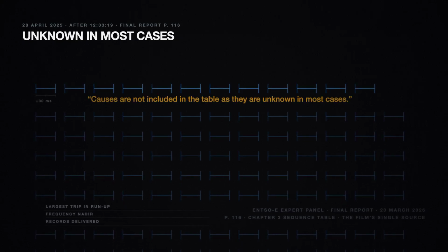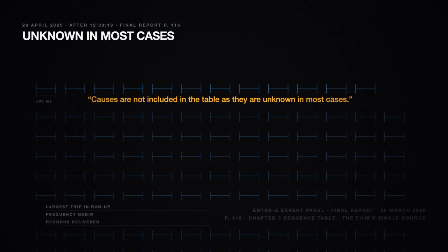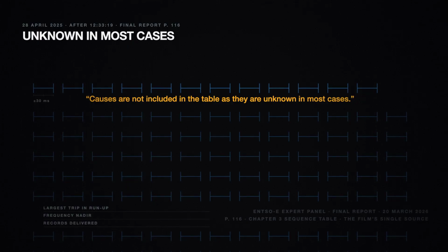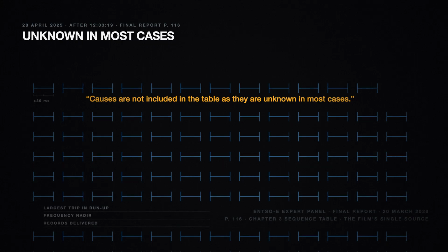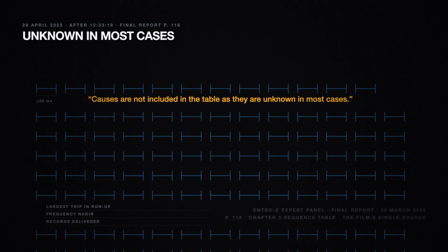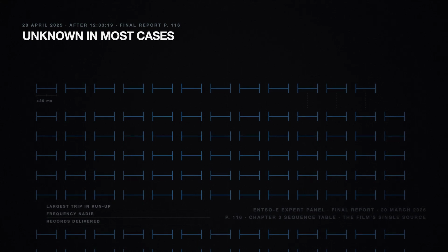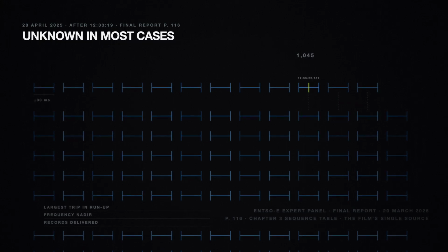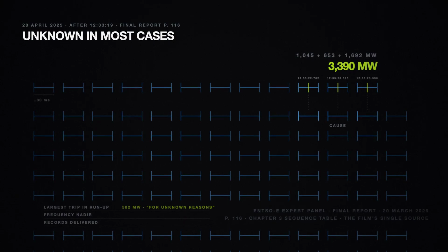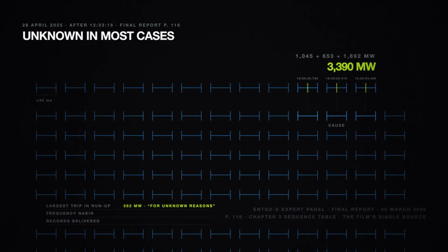Page 116 of the final report carries one line about the table that follows it. Causes are not included in the table as they are unknown in most cases. The table is about 60 rows of generation lost after 12:33 and 19 seconds. No cause is attributed to any of them. The nuclear fleet is in there. 1,045 megawatts, then 653, then 1,692, 3,390 megawatts, and no reason recorded. The largest single trip in the run-up is the same. The Badajoz evacuation line, 582 megawatts, for unknown reasons.